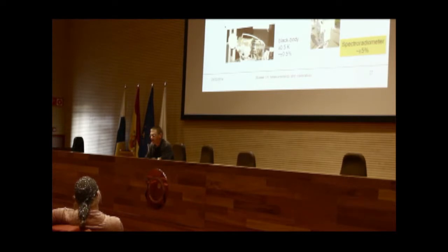And this is all happening in national metrology institutes. So that's not something you are doing in your own home laboratory, but this is done by very specialized laboratories, a few of them in the world. And these laboratories, in turn, calibrate lamps that you yourself can buy and bring to your home institute to perform your own calibration. This is what you can see on the top right corner, called the transfer standard. These are those 1,000-watt lamps that we have in our own laboratories, usually 1 or 2, and that form for us our reference.